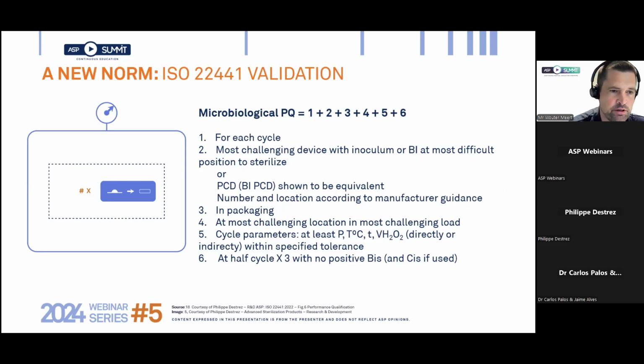And if you look more closely, then you see how a validation runs. You need to have a microbiology performance qualification, and all 6 points need to be there at the end of the validation. That means you need to do it for every cycle. You need to find the most challenging device with an inoculum or a BI in the most challenging position of your sterilizer. You make sure that it is in packaging, and that's important to take into account, because it depends if you're using more than one type of packaging. The packaging needs to be compatible, of course, with hydrogen peroxide.